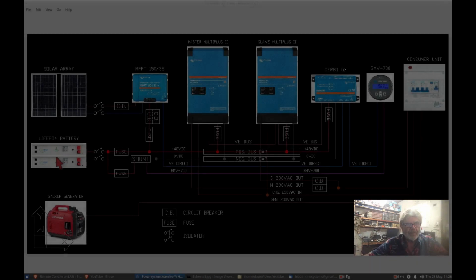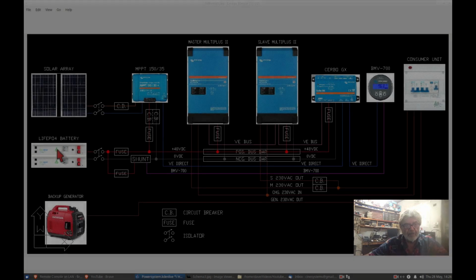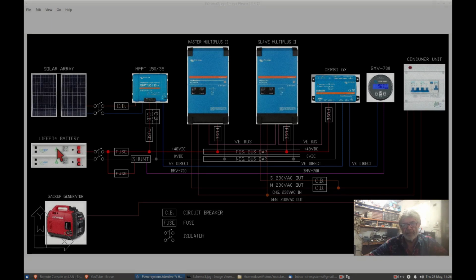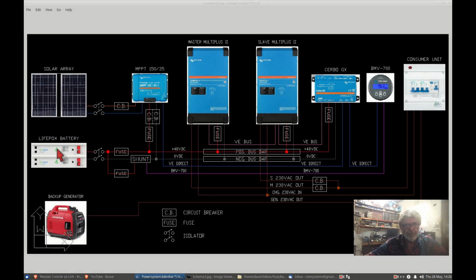Here is the battery. I currently run a Power Plus Eco 4840p lithium iron phosphate battery. It's a 4 kilowatt hour at 48 volts. Self-managing, so it doesn't need any particular data connection to the main system. However, the system is programmed to the parameters Power Plus provide. So pos and neg come out of the battery into a 2-pole isolator. Then we have a main fuse in the positive line and direct connection to the positive bus bar. The negative line comes out of the isolator to a shunt, a Victron shunt, and the system side of the shunt connected again to the negative bus bar.